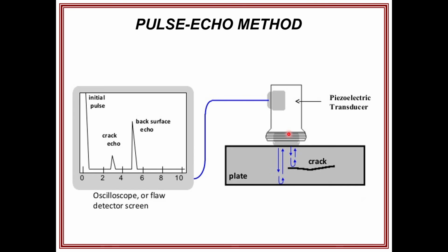So here the ultrasonic waves are traveling from here. These ultrasonic waves having a particular wavelength, and the echo time can be recorded. The wavelength and echo time both can be understood. So from that we can calculate the thickness of the material, that is the thickness here. D, distance traveled, is considered as the thickness of the material. That is, D is equal to thickness is equal to velocity into time upon 2. We'll see that formula.